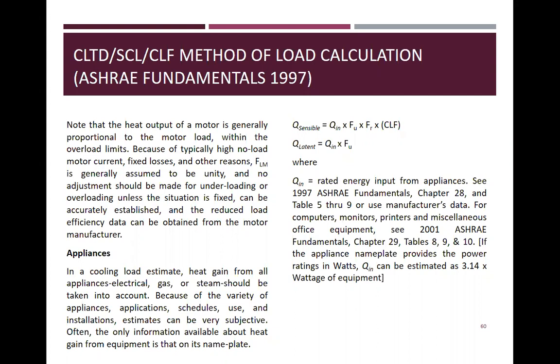So Q sensible is equal to Qn times Fu times Fr times CLF. Q latent is Qn times Fu, where Qn is the rated energy input from appliances. See 1997 ASHRAE Fundamentals, chapter 28, tables 5 through 9, use manufacturer's data. For computers, monitors, printers, and miscellaneous office equipment, see 2001 ASHRAE Fundamentals, chapter 29, tables 8, 9, 10, also 1997. If the appliance nameplate provides the power rating in watts, Qn can be estimated as 3.40 times the wattage of equipment.